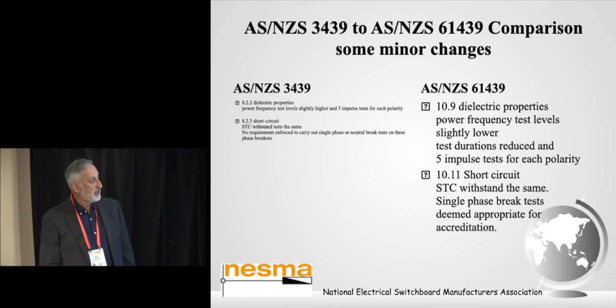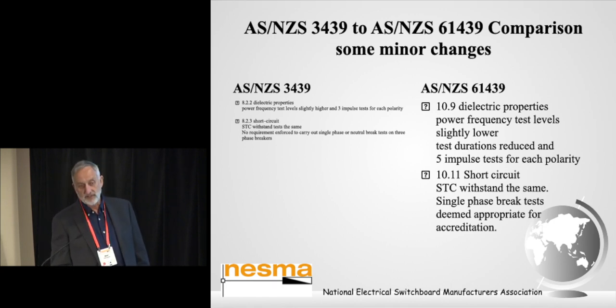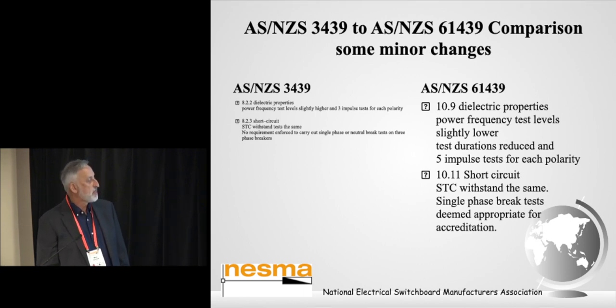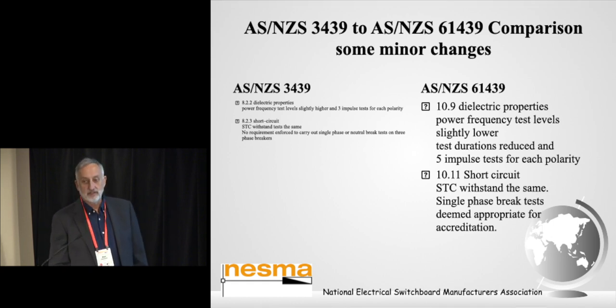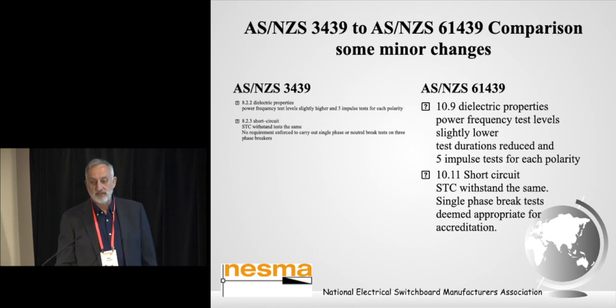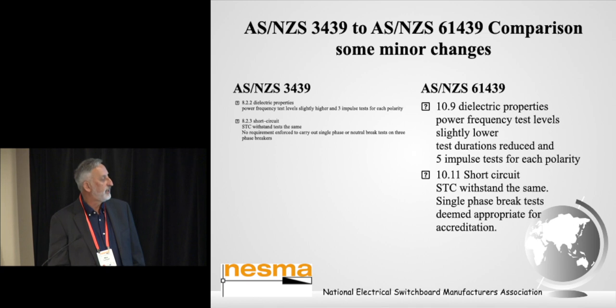And then for impulse tests, we had 5 impulse tests for each polarity. Looking at that, some certification bodies don't see a difference between 3 impulse positive and negative and 5 impulse positive and negative tests, but there is a difference, and compliance theoretically should have an impulse test series with 5 positive and negative tests. The short circuit, the old short circuit clause was 8.2.3. With regard to short time withstand current tests, against the new clause of 10.11, there are no differences. The test is identical, and so there's no change. So if you've got a test of 50 kA for a second under either document, there's no difference in the requirement of the test or the results of the test.